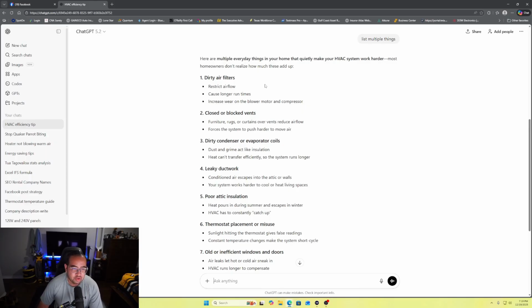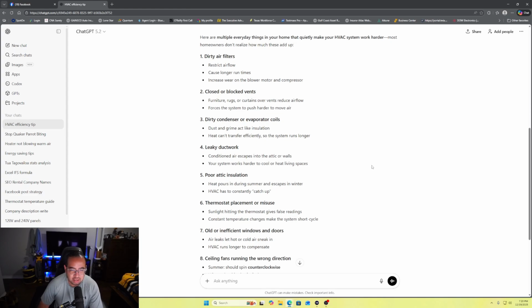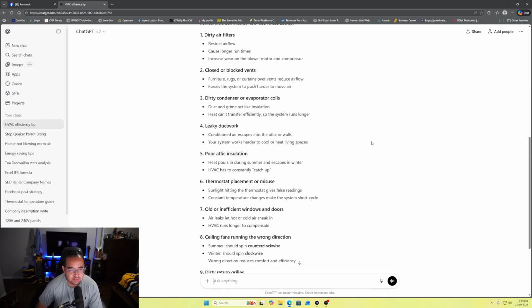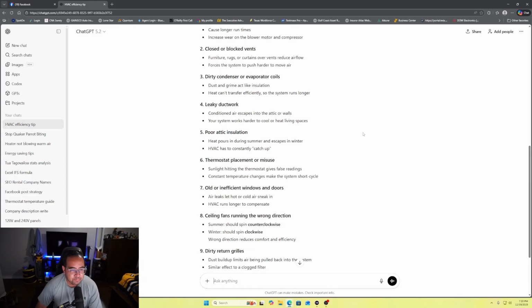But the first one is a dirty air filter, which can restrict airflow. I agree 100%. It will make your unit run harder because there's less airflow coming across that evaporator coil and less heat is being rejected in your home. Closed or blocked vents, that's going to stop any CFMs getting to your rooms. Dirty condenser or evaporator coil, same thing as a dirty filter. It's not going to allow that heat to be rejected out of your condenser, and there's not going to be a lot of air coming across that evaporator coil.